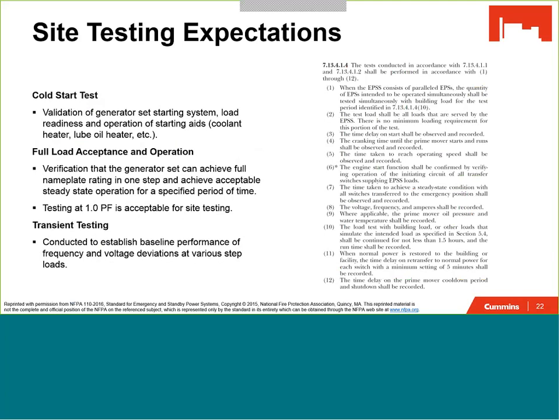What you're seeing on the right-hand side there is taken directly out of NFPA 110. Similar to prototype testing, there's a lot of information requested or required by NFPA 110, but I'm going to talk about some things that aren't necessarily called out, or I'll share a bit more detail about some of these specific tests. A cold start test is fairly common, and don't let the term cold start worry you too much. The intent here is to test the capability of the generator set to start as if it was called on in an emergency situation and meet any start time requirements that you may have. So this is really testing the starting system and any starting aids, as well as the power system scheme, and ensuring the system is meeting your reliability goals.